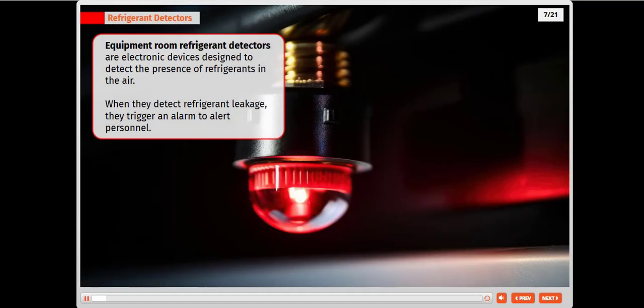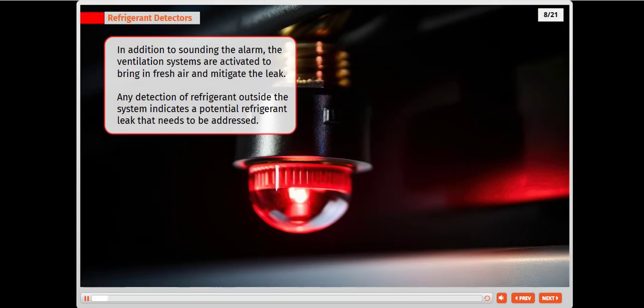Equipment room refrigerant detectors are electronic devices designed to detect the presence of refrigerants in the air. When they detect refrigerant leakage, they trigger an alarm to alert personnel. In addition to sounding the alarm, the ventilation systems are activated to bring in fresh air and mitigate the leak. Any detection of refrigerant outside the system indicates a potential refrigerant leak that needs to be addressed.